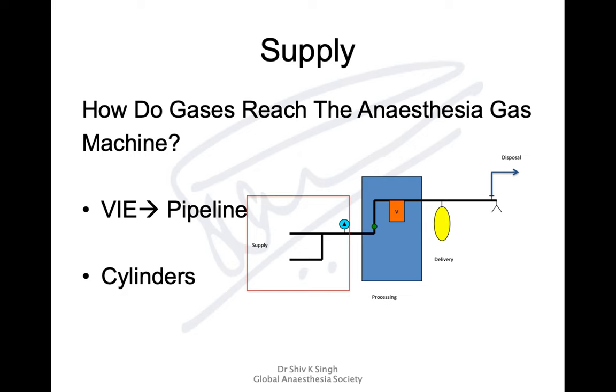Supply is basically about how gases reach the anesthesia machine. They can come through the pipeline from a VIE or banks of cylinders in the manifold room, or from cylinders at the back of the machine.